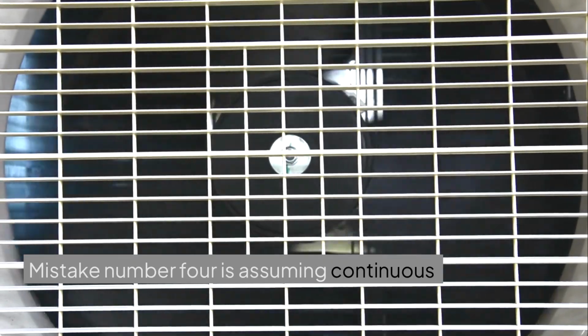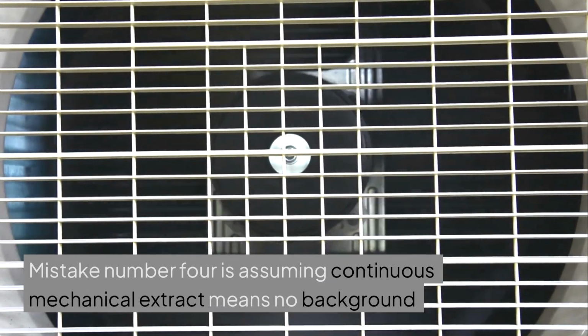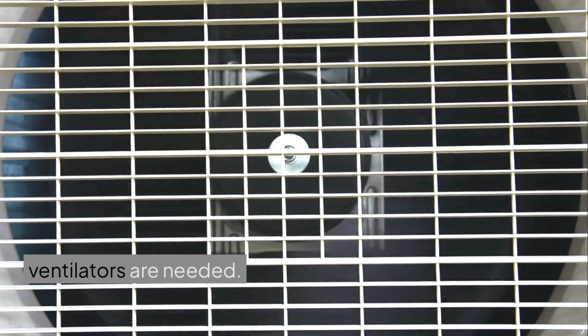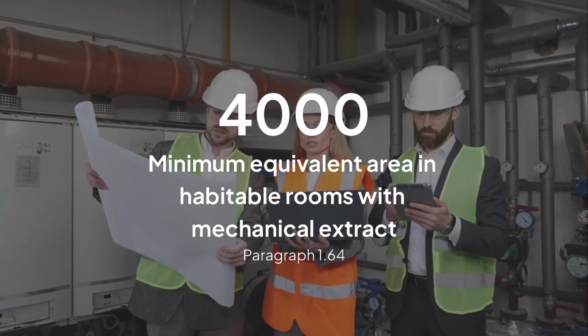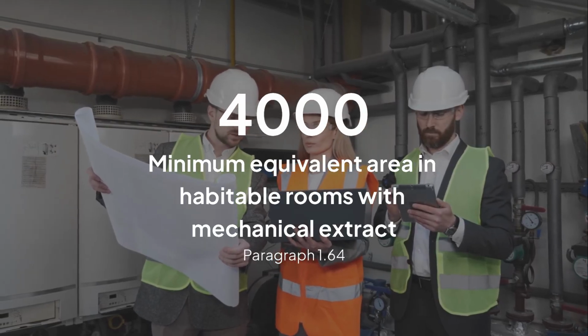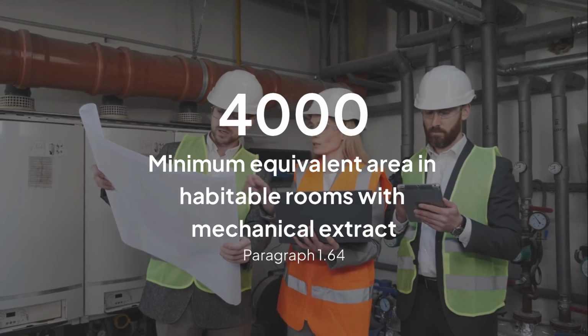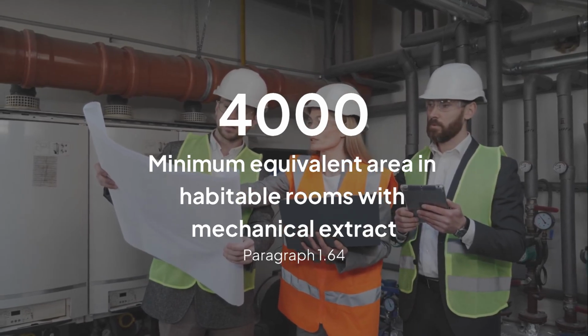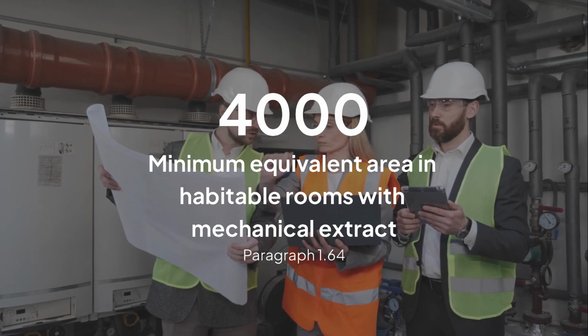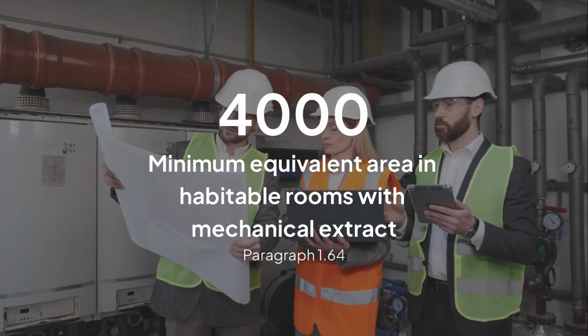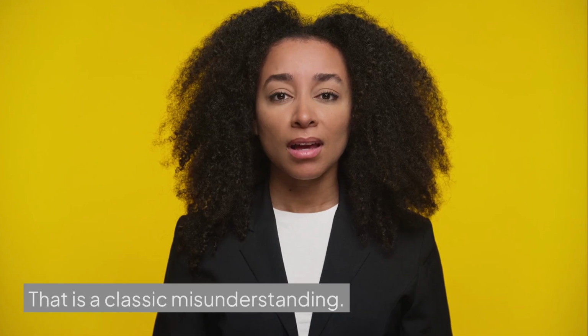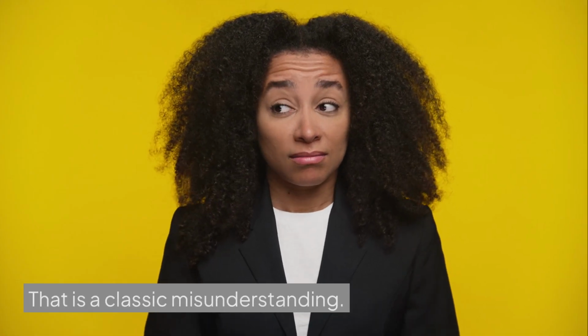Mistake number 4 is assuming continuous mechanical extract means no background ventilators are needed. Paragraph 1.64 says that where continuous mechanical extract ventilation is used, background ventilators should not be in wet rooms, but each habitable room should still have a minimum equivalent area of 4,000 square millimeters. That is a classic misunderstanding.